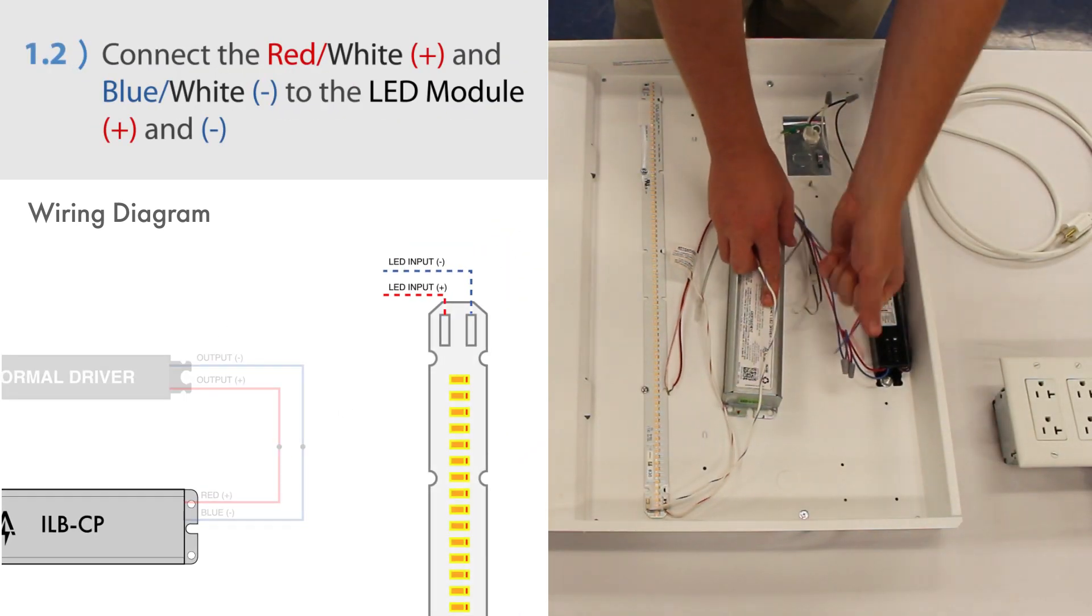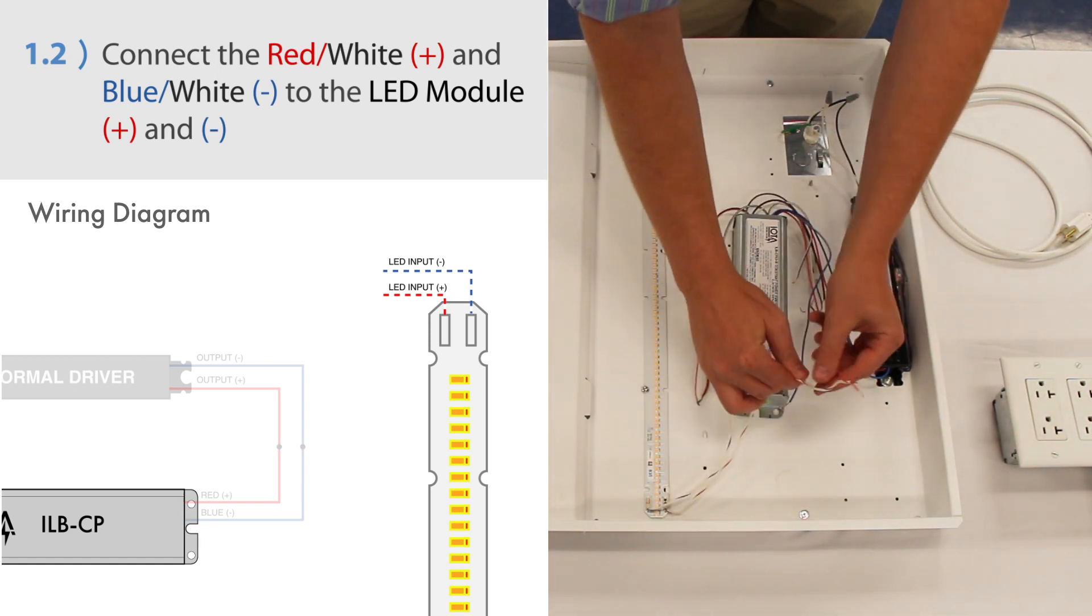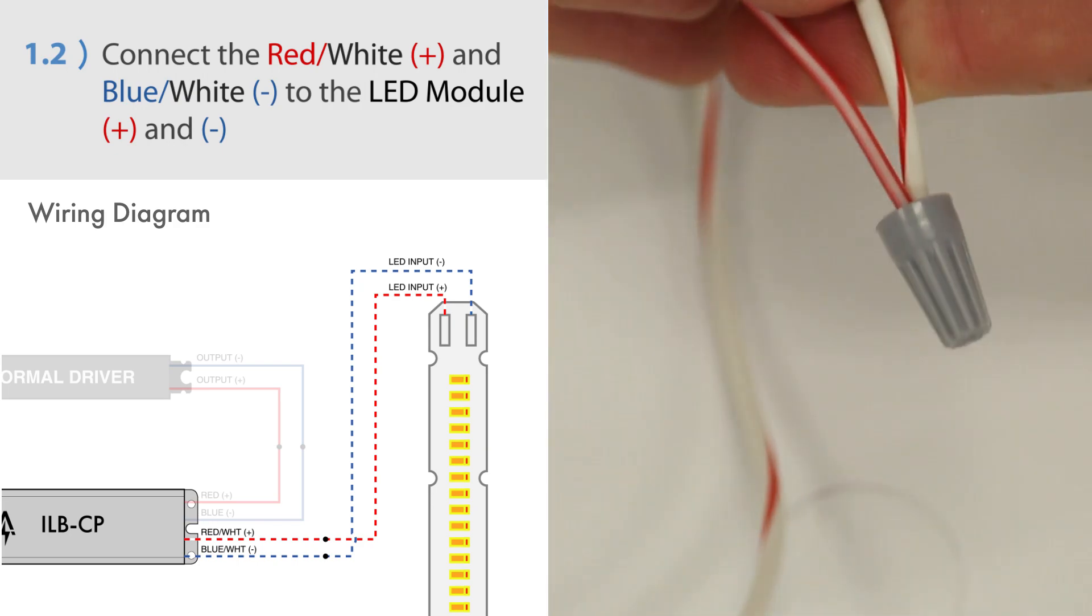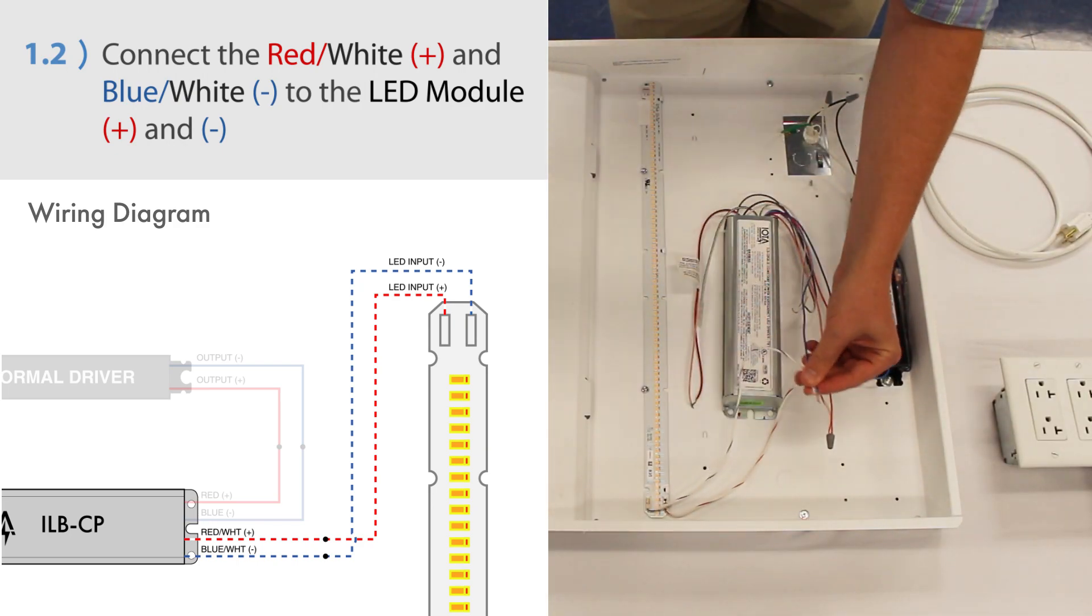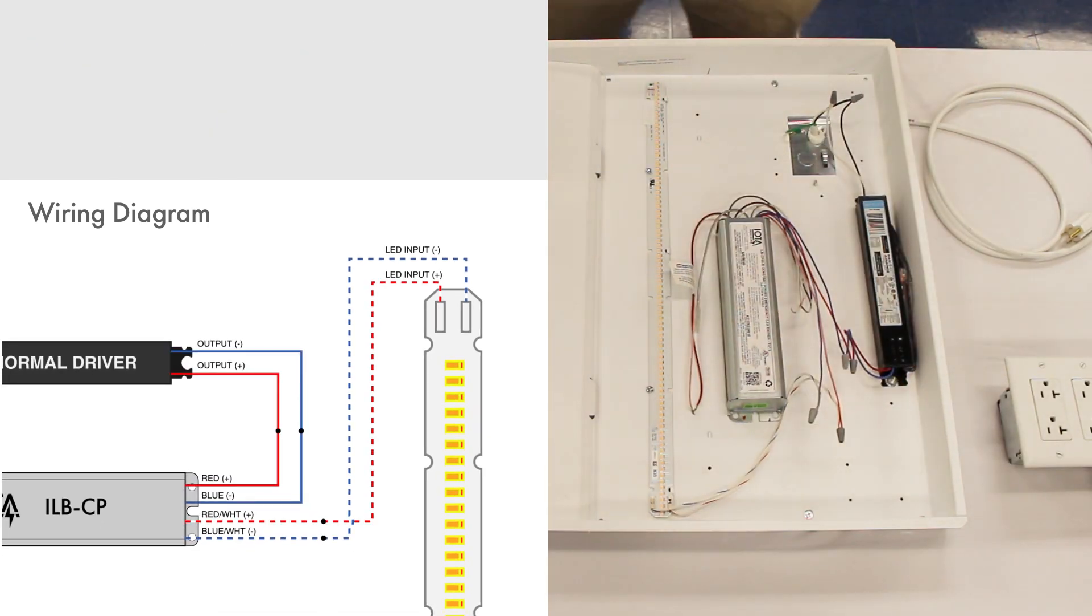Next, connect the red-white positive and blue-white negative wires from the ILB-CP to the positive and negative inputs on the LED module. Again, be sure to observe polarity. Afterwards, the output of the ILB-CP will be wired successfully.